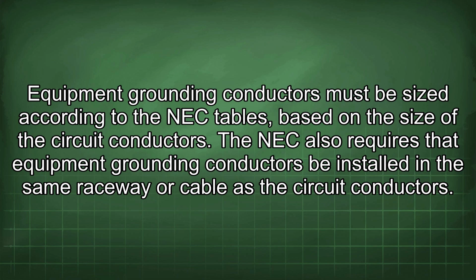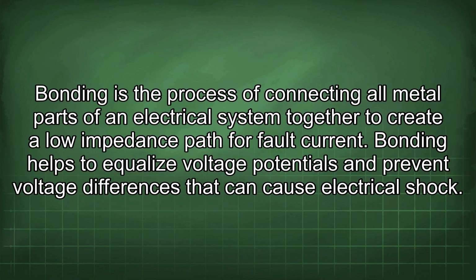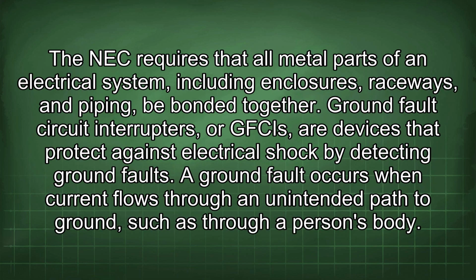Bonding is the process of connecting all metal parts of an electrical system together to create a low impedance path for fault current. Bonding helps to equalize voltage potentials and prevent voltage differences that can cause electrical shock. The NEC requires that all metal parts of an electrical system, including enclosures, raceways, and piping, be bonded together.